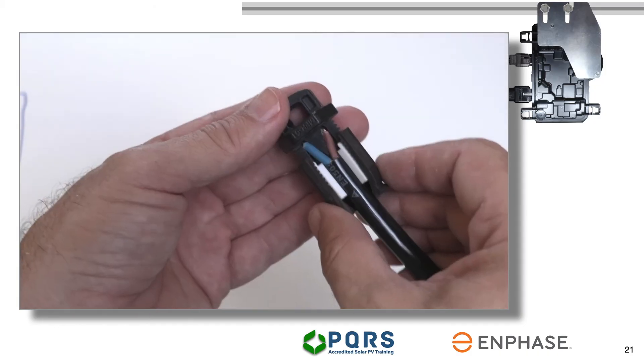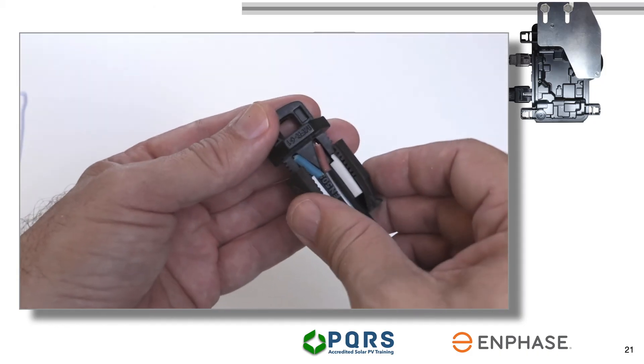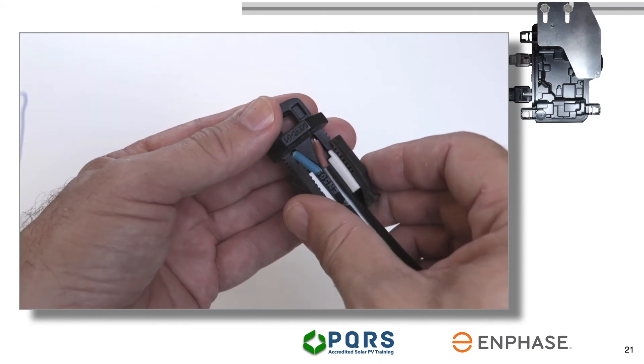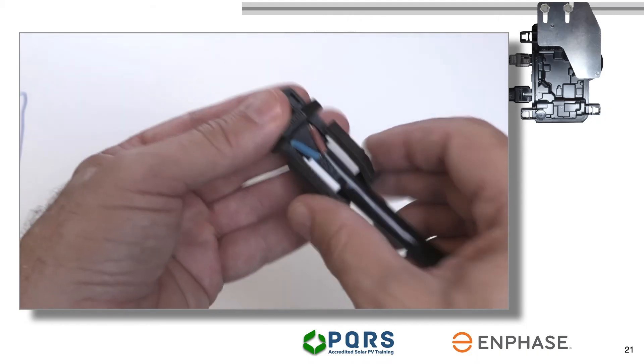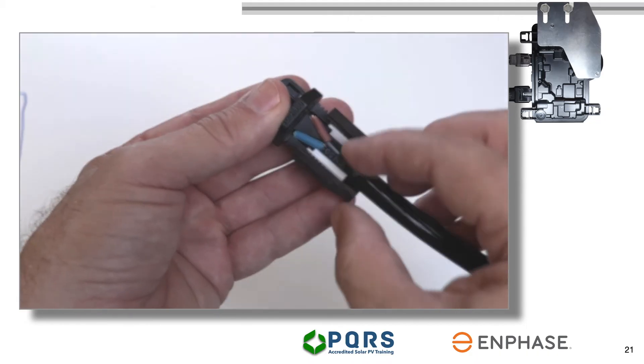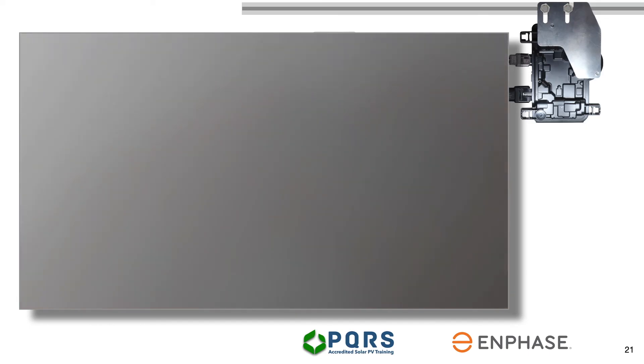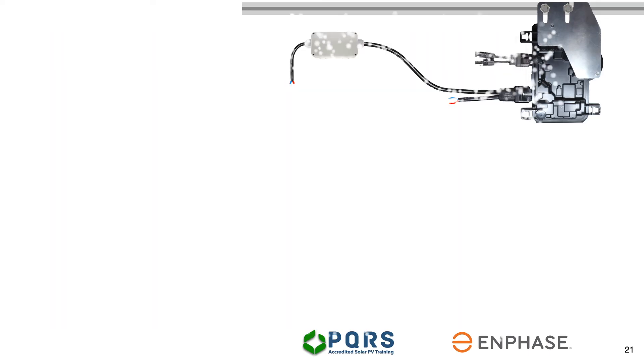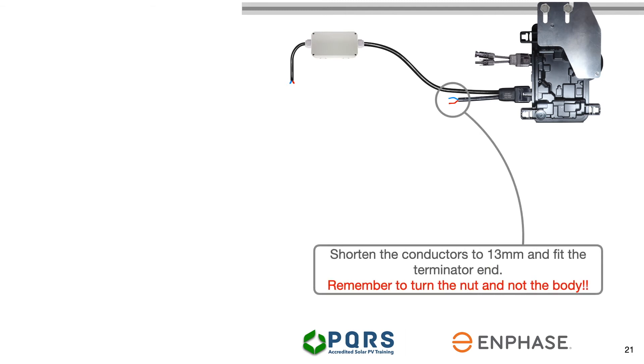Remember that a Q-terminator can only be used once. If the nut is undone for whatever reason, the entire Q-terminator is destroyed. The conductors going into the Q-terminator should be in the region of 13mm long. So let's shorten those quickly.